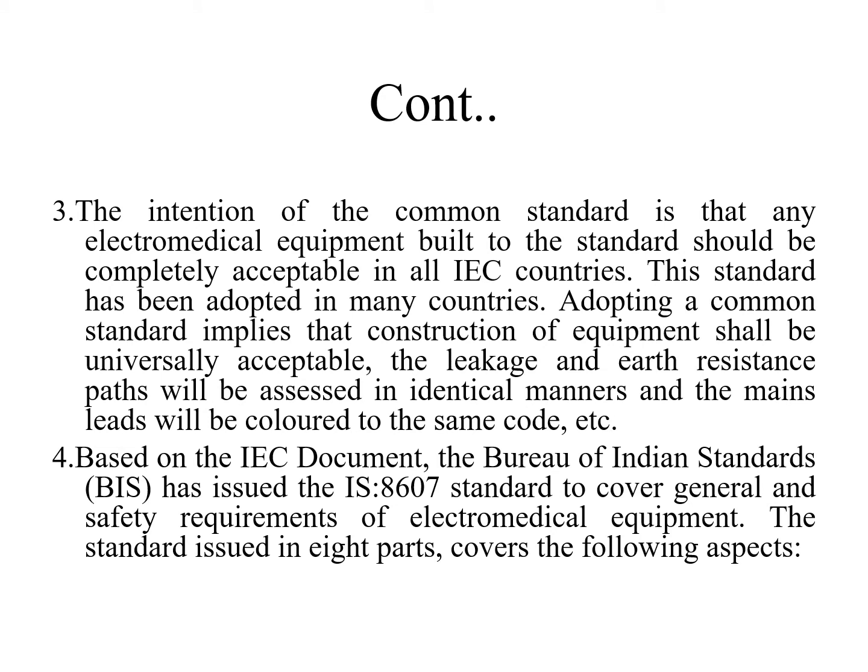The intention of the common standard is that any electro-medical equipment built to the standard should be completely acceptable in all IEC countries. This standard has been adopted in many countries. Adopting a common standard implies that construction of equipment shall be universally acceptable; leakage and earth resistance paths will be assessed in identical manners, and the mains leads will be colored to the same code, etc.